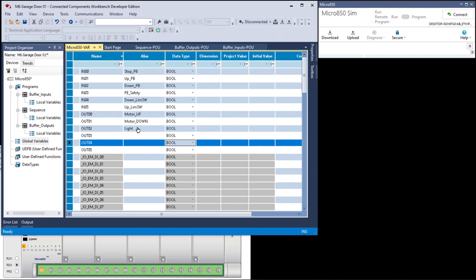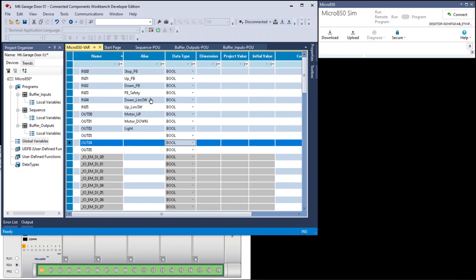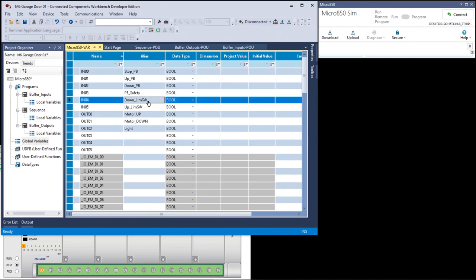Input three is PE safety. Input one is the up push button. Now you see that I have changed all these to match what's in the book. Now in the book they were still out of order in the column. It was input one, then input zero, then two, three, four, five. So input zero is stop push button. Input one is up push button. Input two, down push button. Input three, photo eye safety. And then four and five are down and up limit switches. Now notice I changed the text. In some cases I used all uppercase DOWN and then I had limit spelled all the way out. In some cases I spell switch all the way out. In other cases I use uppercase S, lowercase W, or just uppercase SW for switch. Now it should have been limit switch. See they do match. So it's a good idea to stick to the same nomenclature in one program. Don't vary it within a program.